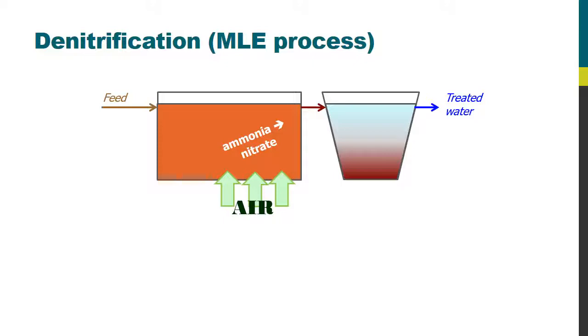But that biological tank also contains another zone which is fed from the sediment of the secondary clarifier. And those solids contain nitrate enriched sludge which is fed into the so-called anoxic zone of the process tank.